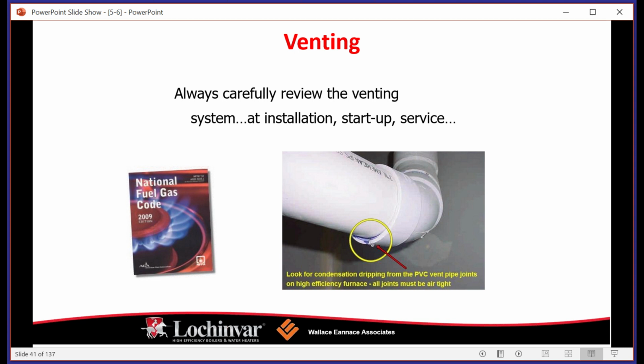Okay, review the venting system at installation, at startup, at service. Again, the National Fuel Gas Code Book is going to run through this very comprehensively. But also in your install manuals, there is going to be a section that lays out exactly what size of pipe you're going to need, how far you can take it, and your best practices for where you should be landing everything.